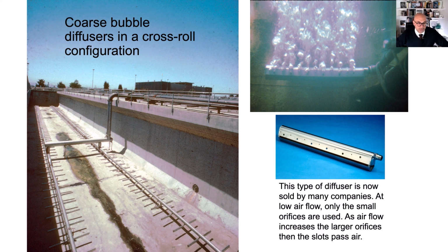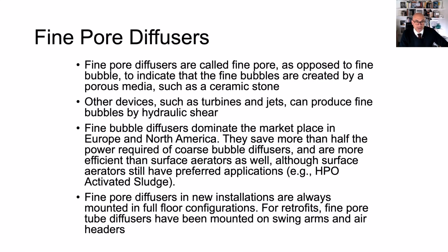But a full floor will have a third row in the middle there, and it's not for municipal anymore, but definitely for industrial they still have a market. This releases a lot more air from the sparger, and over a larger area, of course, because they're longer, and being made of stainless steel, they're supposed to last practically forever.